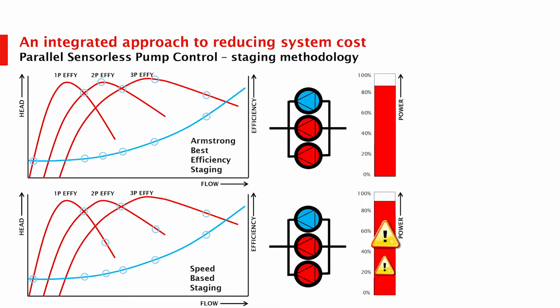So on this slide, this is probably the most technical slide I have. If you want to tune out for 2 minutes, that's okay. If you're really interested in how parallel pumping works, pay attention to this slide. It is probably the most indicative slide I have of how parallel pumping actually works. On the bottom is the traditional approach to speed-based control, and this is not just pumps, it's fans, chillers, pretty much everything.